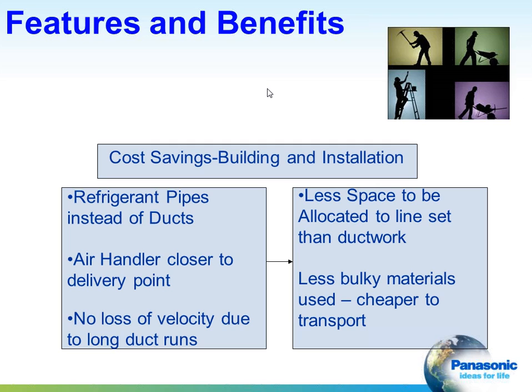There's cost savings to be gotten from these systems, both in the construction of a building and installation. We're running refrigerant pipes instead of ducts. It takes up less space, less bulk. The air handler is closer to the delivery point, and there's no loss of velocity of airflow due to long duct runs. These factors allow a smaller, shorter ceiling cavity, and less bulky materials are used, and that's cheaper to transport.